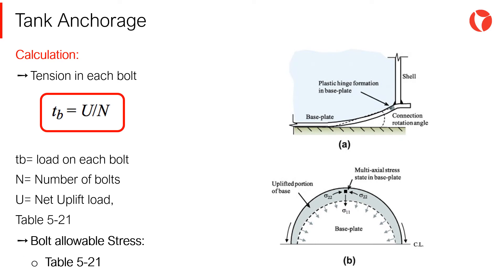According to section 5.12 of the code, tension in each bolt is calculated according to the equation displayed on screen. Where TB is the load on each bolt, N is the number of bolts, and U is the net lifting load, per table 521A of the code.